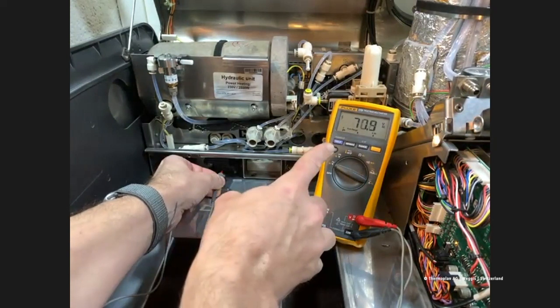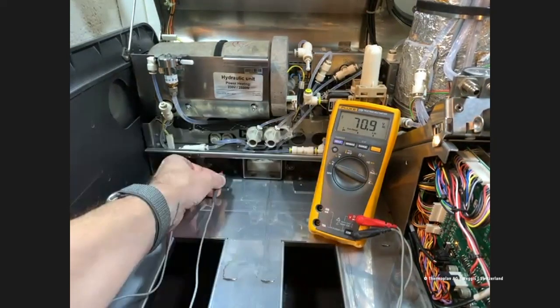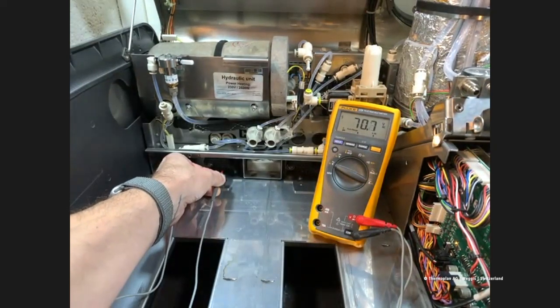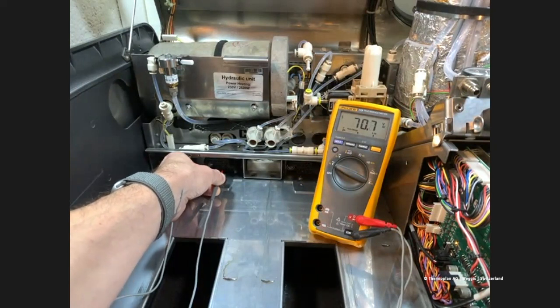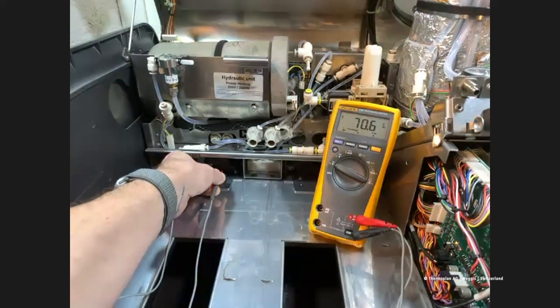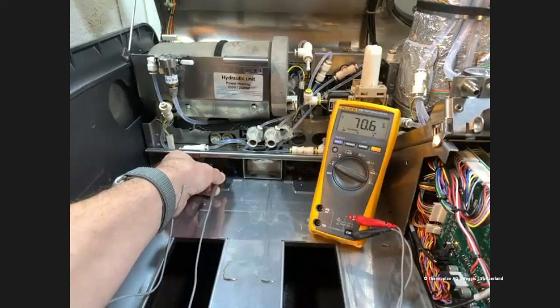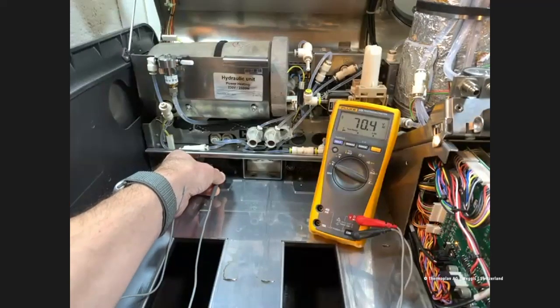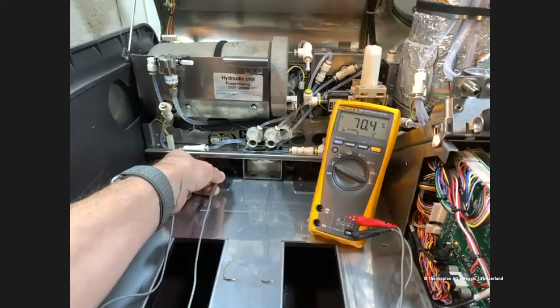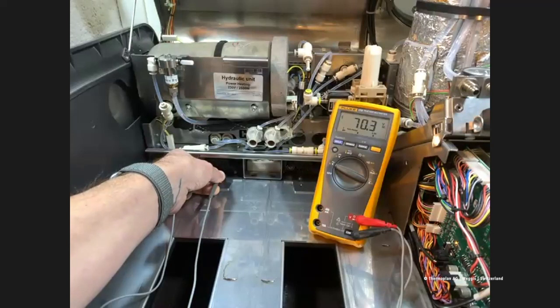You'll notice on the meter we have 70 volts AC. That is a ghost voltage because we use a triac to switch rather than a straight switch. We get a little bit of ghost voltage there, but it's nothing to worry about. It's not actually 70 volts of power going to the heater.